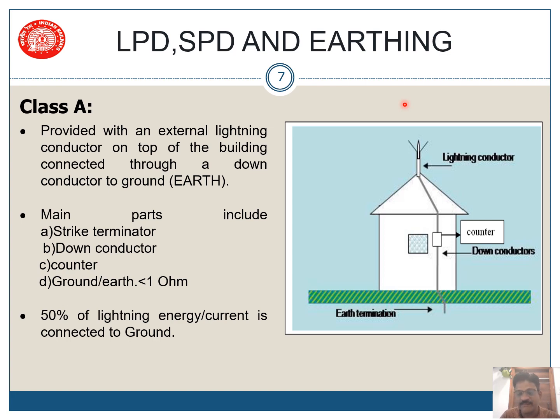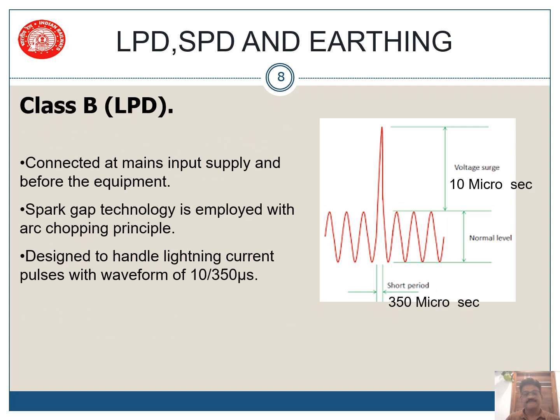That is the maximum current that is observed in India. So let us say 200 kilo amps, that is around 2 lakh amperes of current, is developed. In that, almost 50%, that is 100 kilo amps of current, is directly sent to earth if you have a good class A protection.